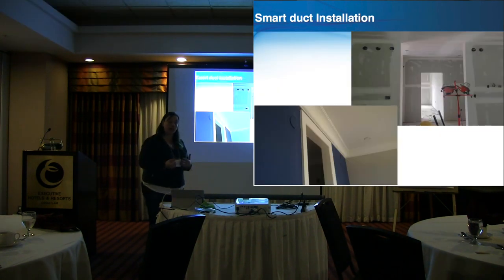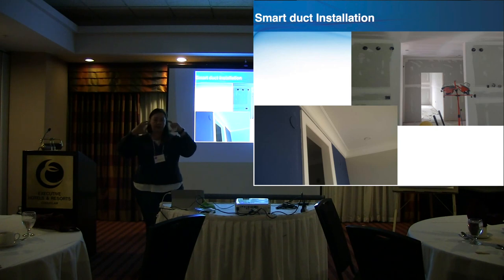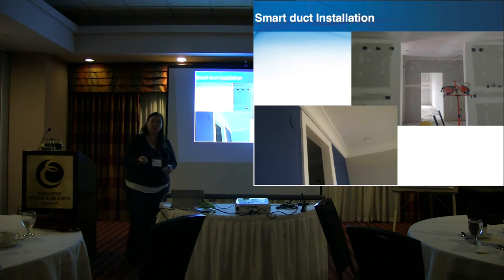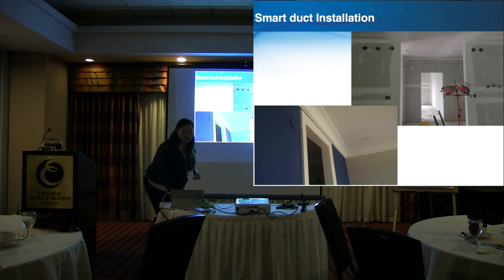And so we do pair heads together, and that just gives it even more push. So with that 9 feet of throw, pairing them together, it gets even more oomph behind it. And we are designing these to the heat loss and heat gain based on F280 calcs, room by room. So we design each house for what it needs. And it's really zoned ready because we're designing per floor. So it's a very cool system.